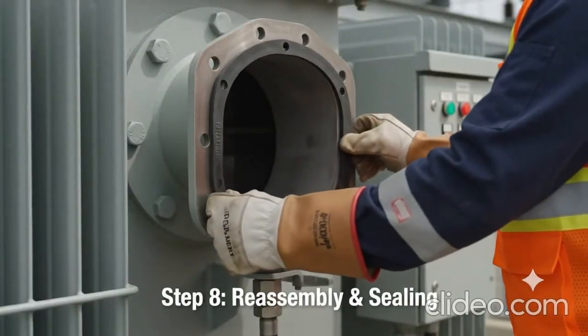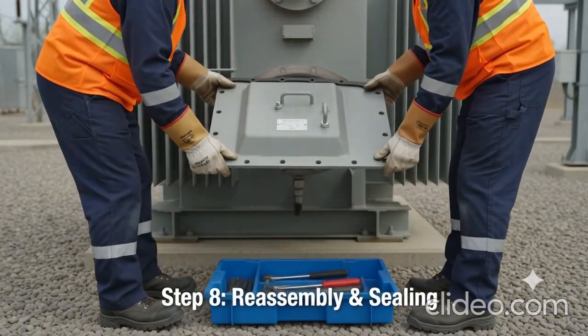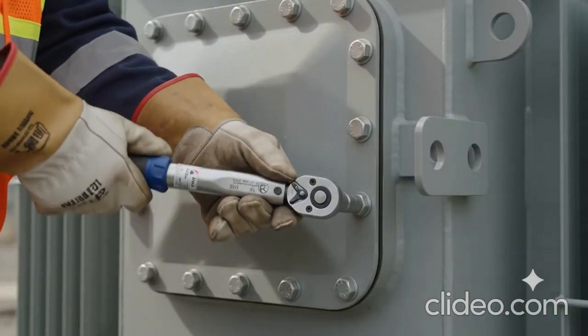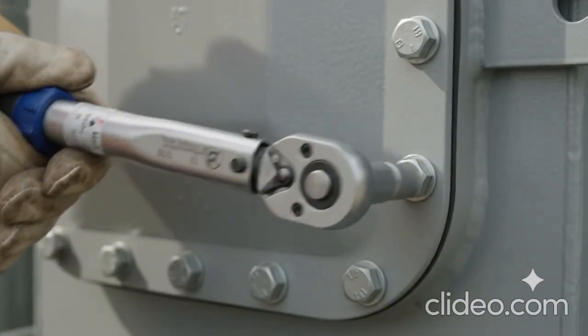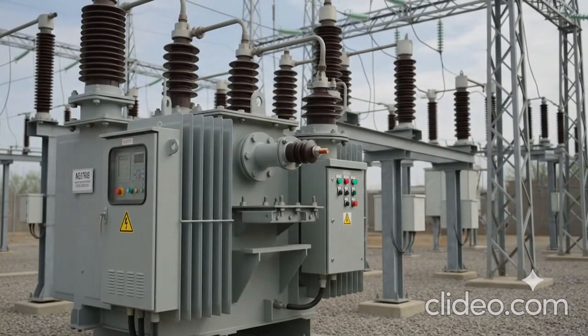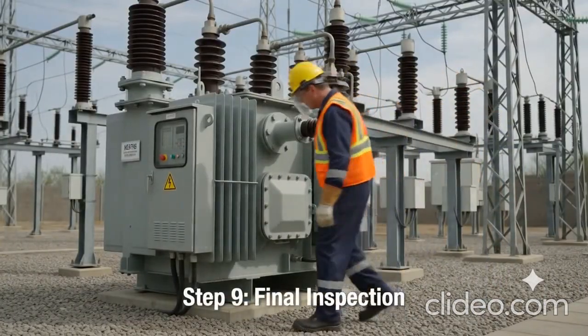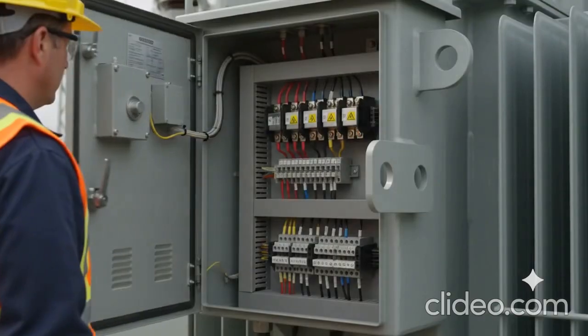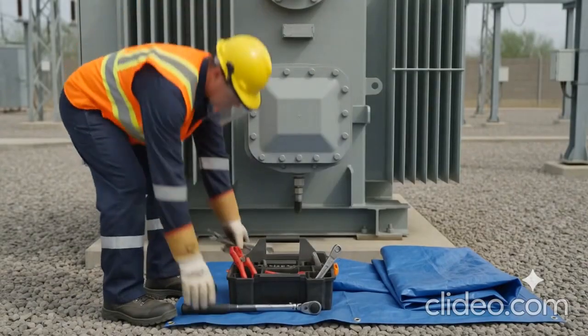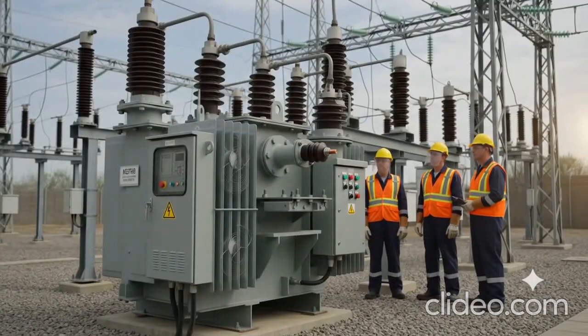After inspection and testing are completed, all open sections are carefully closed. Gaskets are checked and bolts are tightened according to the specified torque. A final inspection is performed. This is to ensure that all connections, covers, and accessories are in their correct condition. Valves, oil levels, and earthing points are checked.